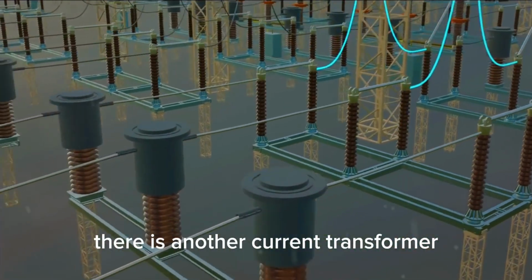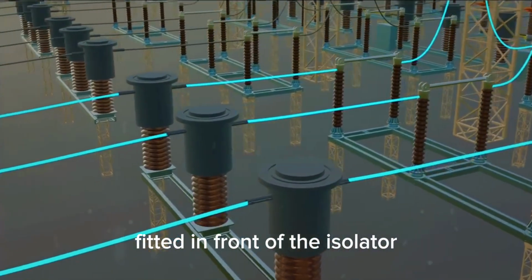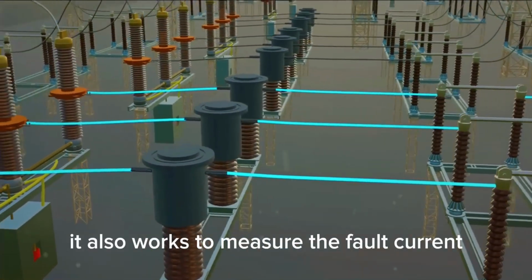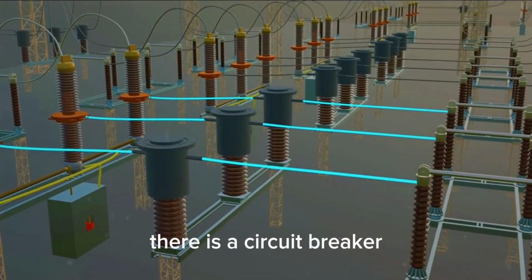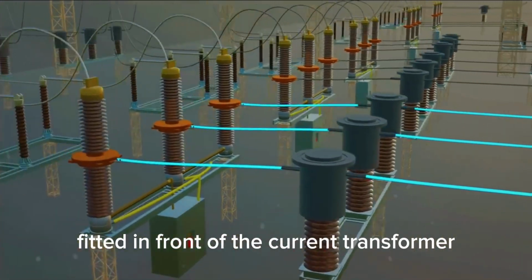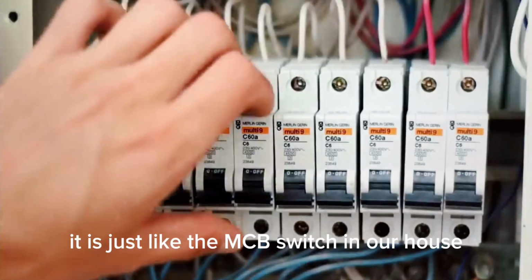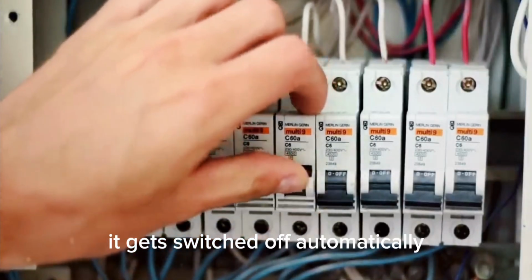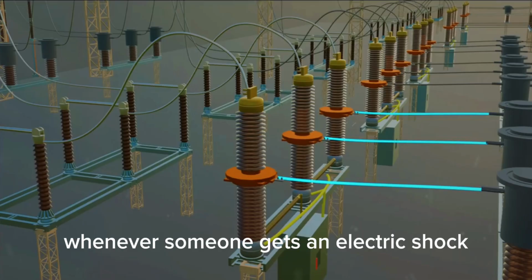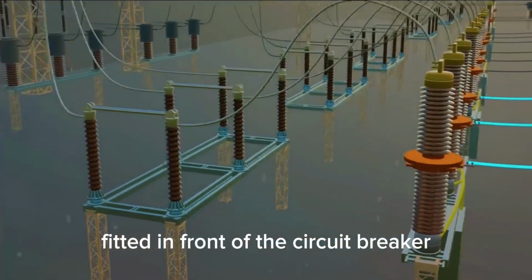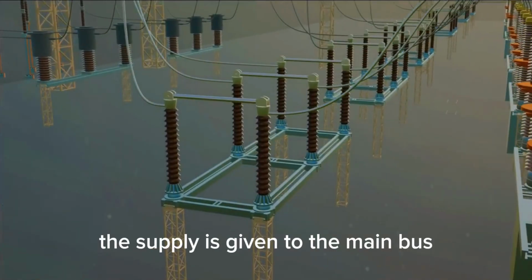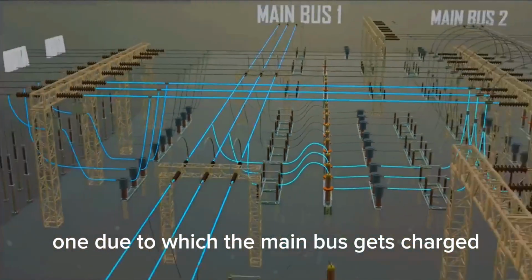There is another current transformer fitted in front of the isolator. We had just talked about it. It also works to measure the fault current. There is a circuit breaker fitted in front of the current transformer. It is just like the MCB switch in our house. It gets switched off automatically whenever someone gets an electric shock. There is another isolator fitted in front of the circuit breaker, and from this isolator the supply is given to the main bus 1, due to which the main bus gets charged.